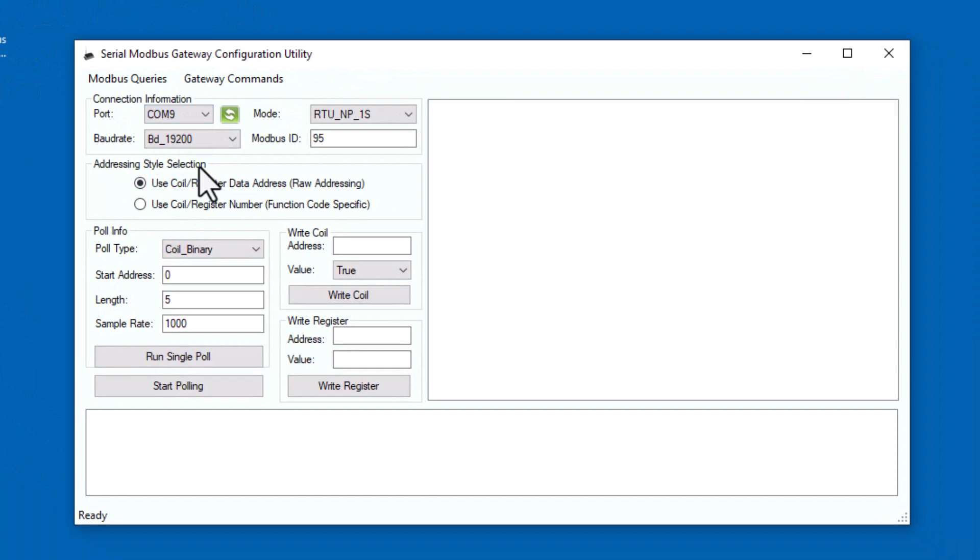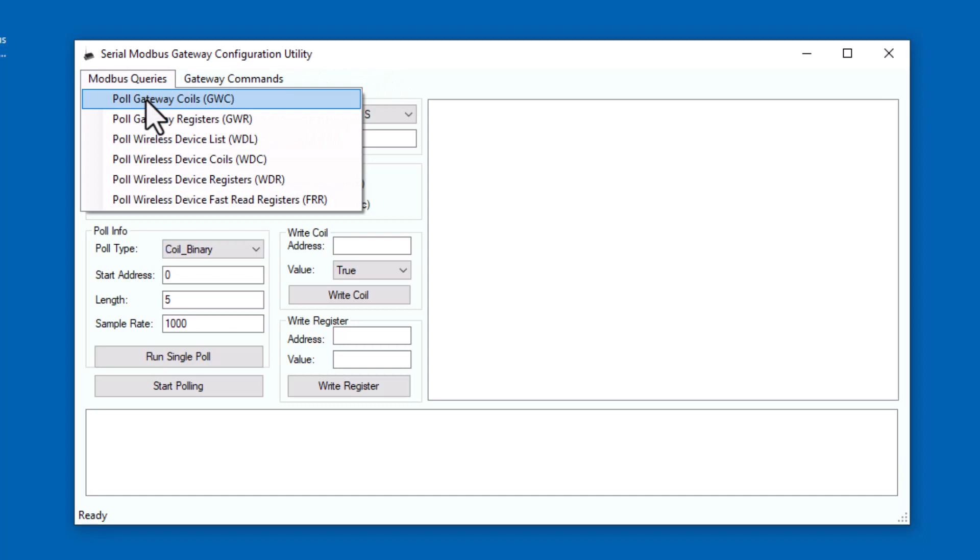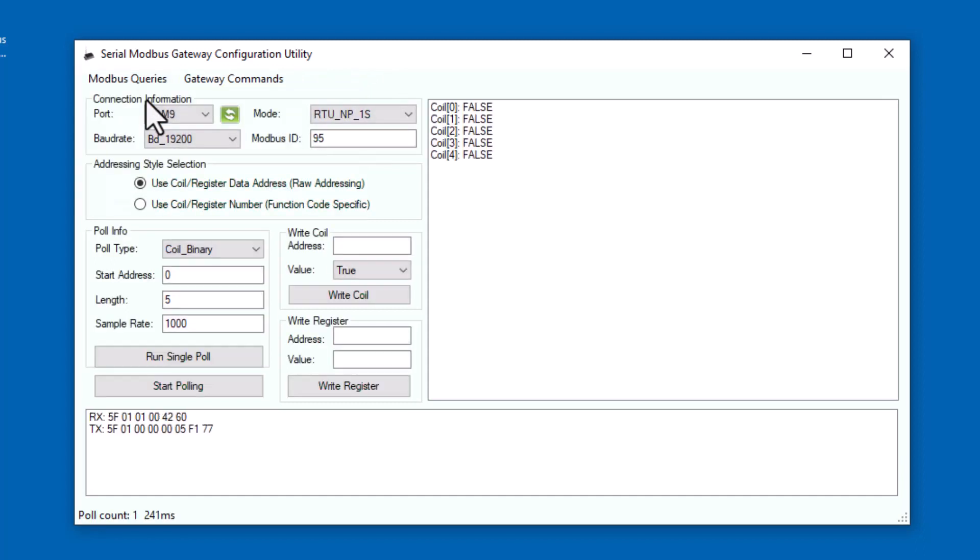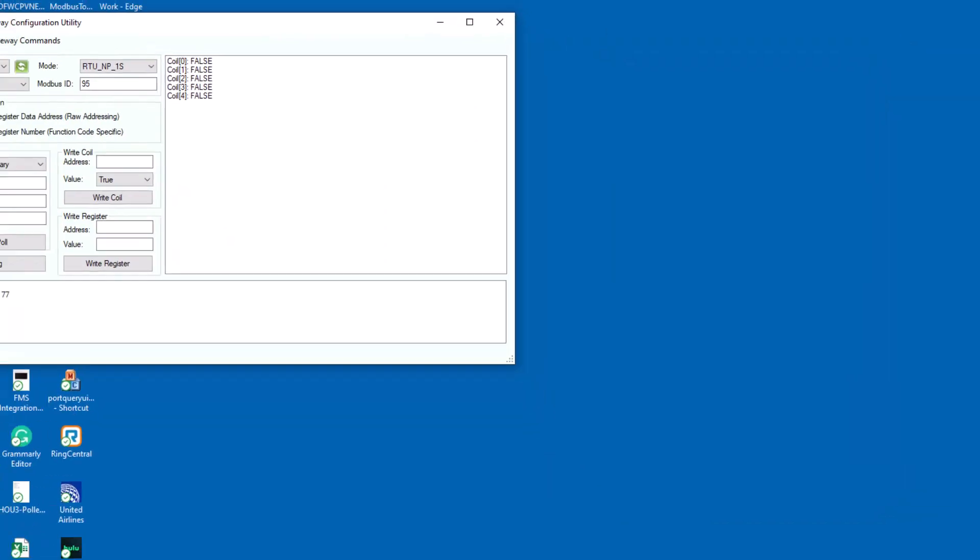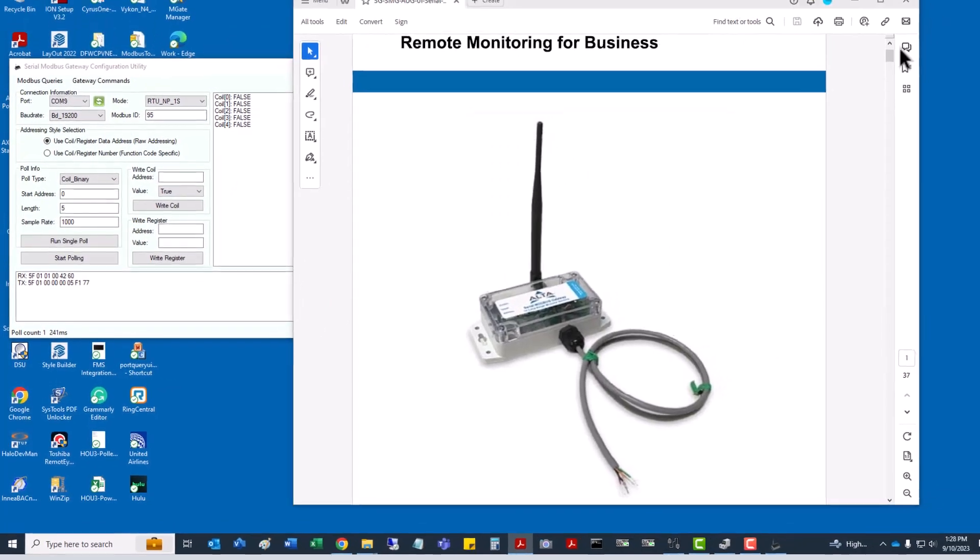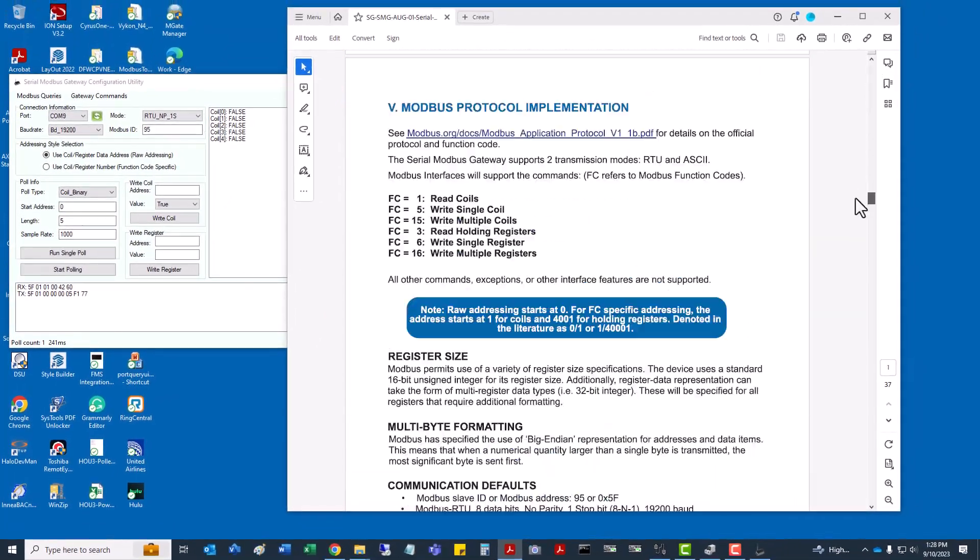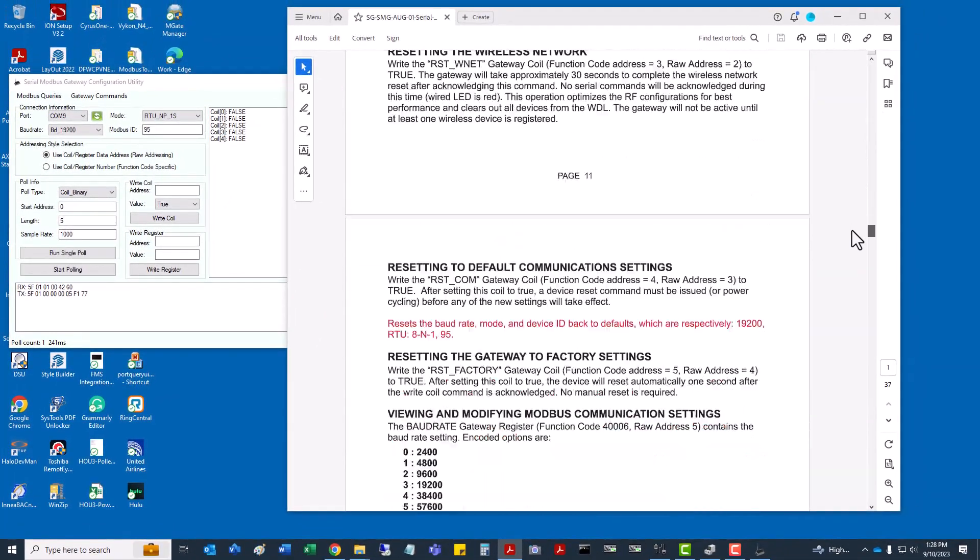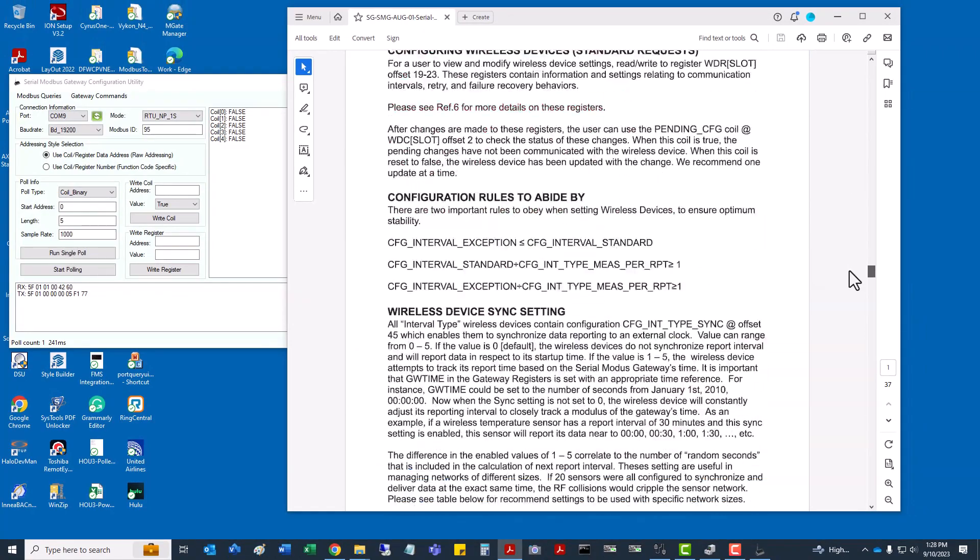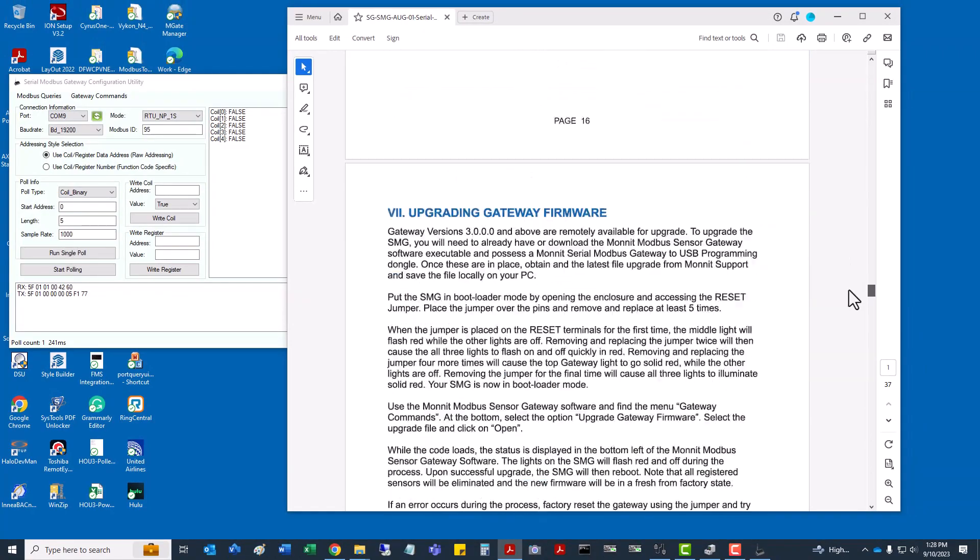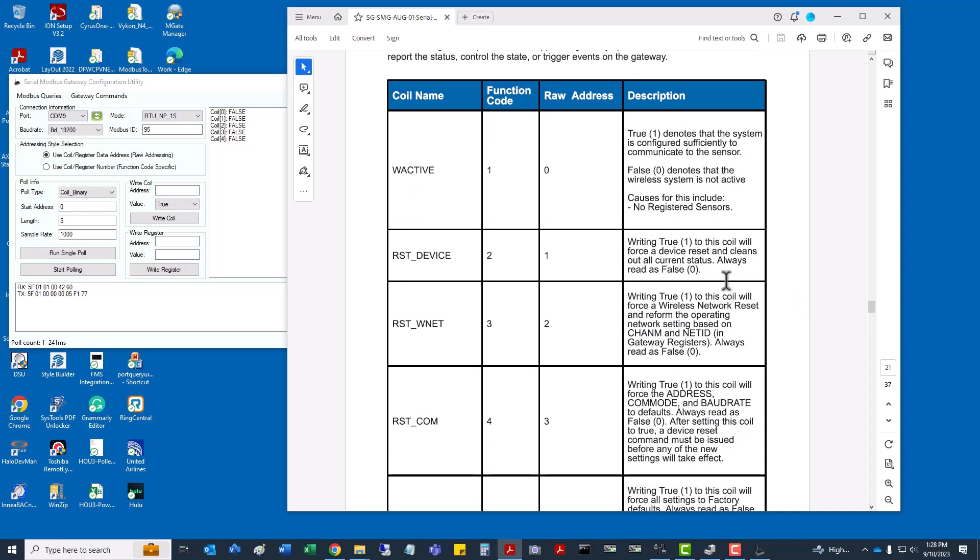Under Ports COM and LPT, my device is the RS-485 isolated port COM9. So all you need to do is select COM9 from that list. If you want to check your communications real quick, you can go here and just pull Gateway Coils. There's coils and holding registers giving you status information of the gateway itself. Here we can see that it's calling out all false for the five coil inputs.